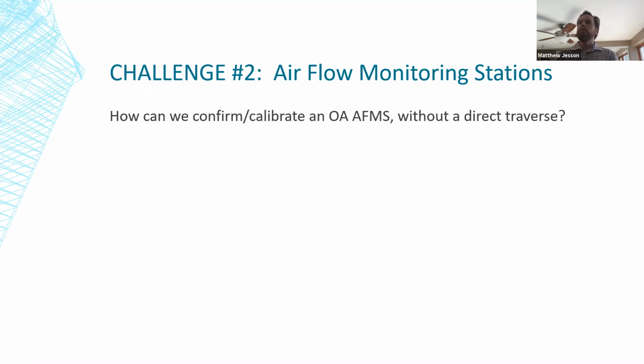So in this instance that we're talking about, with an airflow station located in a minimum outdoor air laminar flow situation, I think that if it's a dedicated minimum outdoor air opening, you've got a much better chance of it being accurate right out of the box. And I'll show you right now kind of what we'll go through on a rooftop unit situation in order to try to confirm or calibrate these airflow stations without getting a direct measurement.